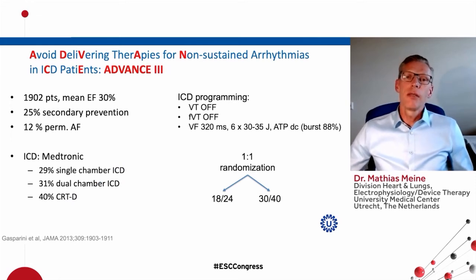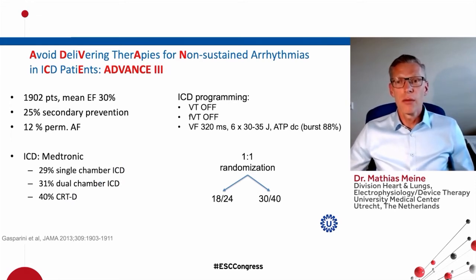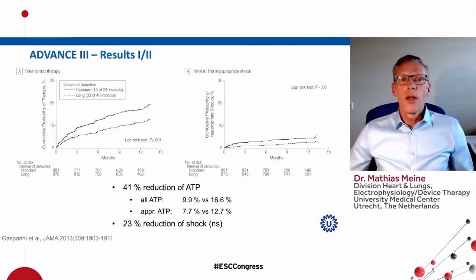The first multicenter randomized controlled trial that showed shock reduction by prolonged detection was the ADVANCE III study. All ICD patients with primary or secondary prophylactic ICD indication, single, dual chamber ICD or CRTD were included. All ICDs were programmed with one VF zone above 188 beats per minute and ATP during charging was turned on. Randomization was in two groups with short detection, 18 out of 24, and long detection, 30 out of 40 NIDs. In the long detection group, less ATP and shocks were delivered.